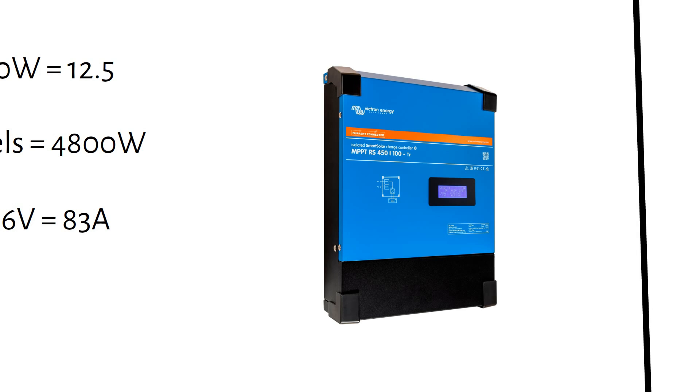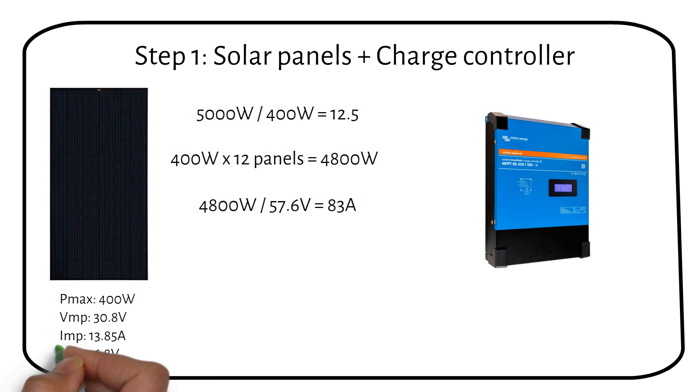Almost done. The next step involves calculating the maximum input voltage. When looking at the solar panel specifications, note the open circuit voltage, or VOC, which is 36.8V. We cannot wire all 12 panels in series, because the voltage would exceed the charge controller's 450V input limit.